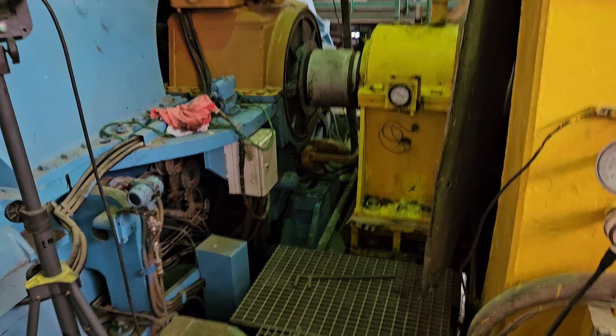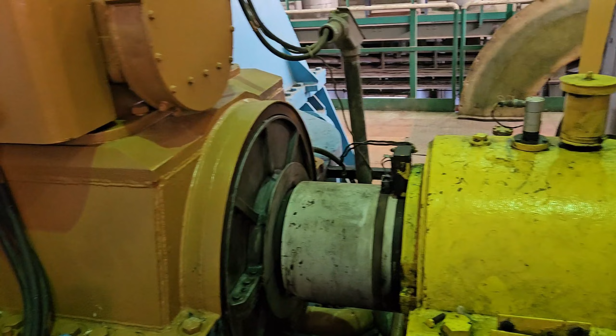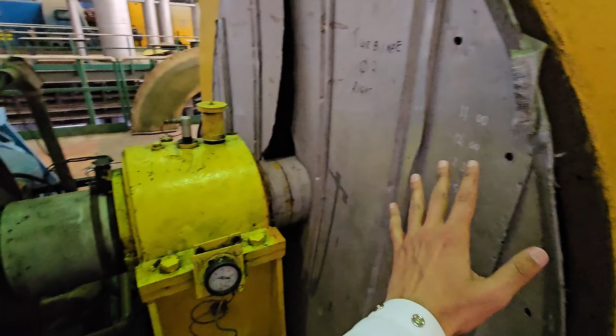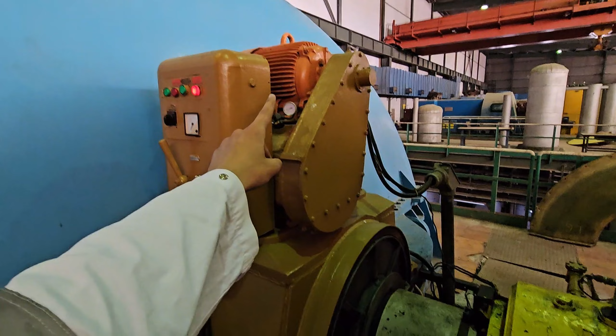Okay, so this is the coupling point that couples the turbine with the generator. And this is a ratcheting motor. Right now it is off. It's not running because maintenance is going on on the turbine and the generator. When the turbine goes on standby mode, this ratcheting motor will be started, and it will rotate the turbine at a very low speed to avoid bending of the shaft. Now we come towards the generator side.